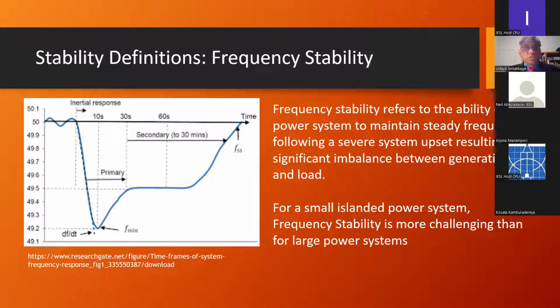The trace shown on the slide is a typical response of frequency of the system to a disturbance. Here, the disturbance is some event creating a mismatch between generation and load. So we can see frequency is dropping. So the mismatch is a generation deficiency situation, load higher than the generation. That can happen if we suddenly add a load, or the generating unit trips off, creating the imbalance between generation and the load.